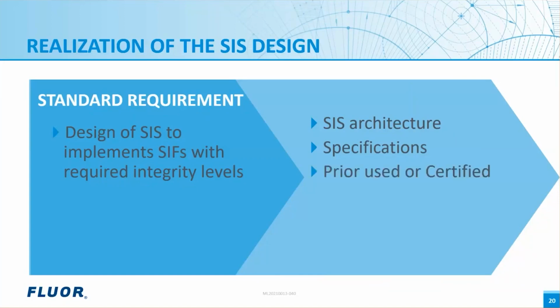A key decision to be made for SIS components is prior use or use of certified devices. Before procurement, make sure the prior use data, or data such as the certificate, its associated report, and safety manual, are thoroughly reviewed to check the suitability for the application and conformance to the integrity requirements.